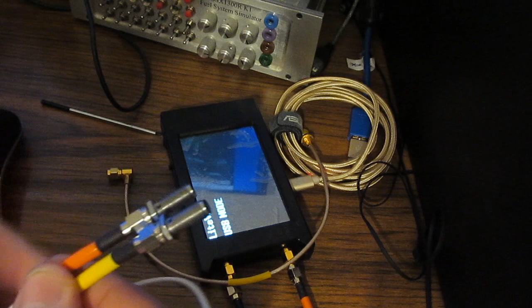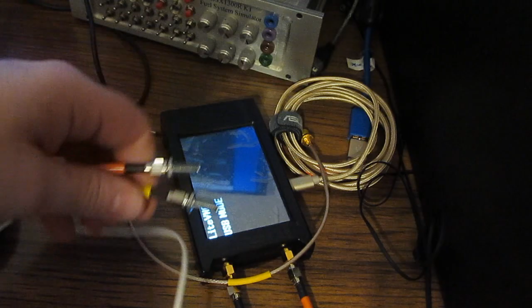Several of the changes that I've made to Solver64 pertain to how the unit is calibrated. Here you can see I don't have anything attached to the VNA other than the two cables. Looking at the main menu, you can see no calibration has been selected. It's currently sweeping between 10 kilohertz and 50 megahertz. And if we look at the Smith chart, you can see we're starting off at an open, and then it moves clockwise around to, looks like J35 or so.